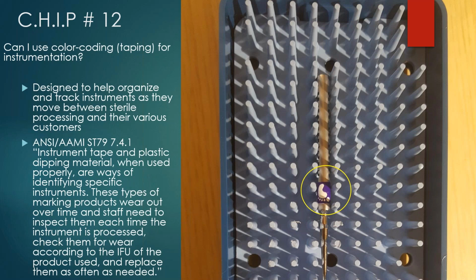These types of marking products wear out over time, and staff need to inspect them each time the instrument is processed. And there we go, because they can be damaged in the first use. And when you're doing that, you're checking them for wear according to the IFU of the product used and replacing them as needed. And that gets very specific. Even application has to be per the IFU. So you're not just checking it. I can tell you, I've not seen a banding tape manufacturer that says five times around. That's not going to be in their IFU.